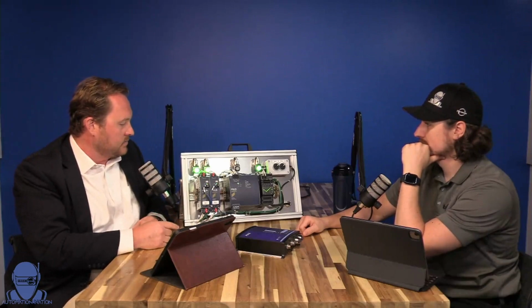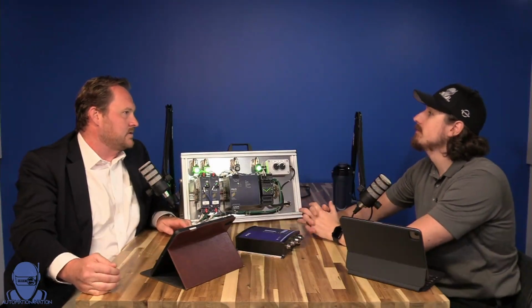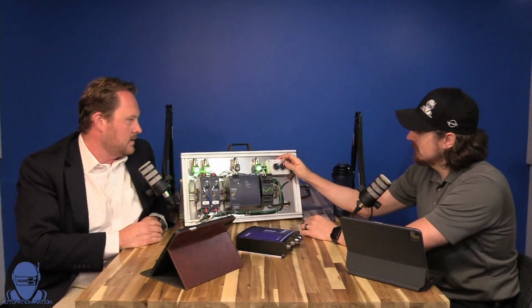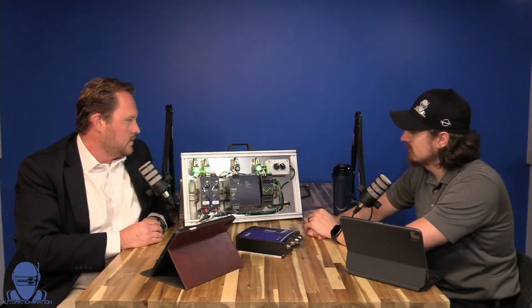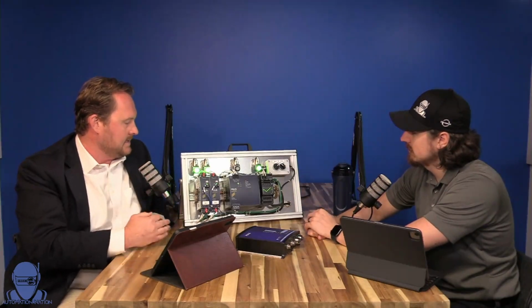So if we were to lose one power supply, or the AC input to one power supply, because a truly reliable or redundant system will have 2 separate AC power sources, right? So maybe the power supply doesn't fail, but the transformer upstream of it does, and so we would lose power. Would you mind switching one of the 2 switches right there? Doesn't matter which. So as soon as the hold up time bleeds off, the light's going to go off.